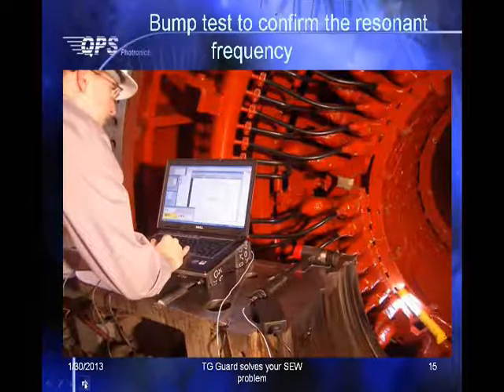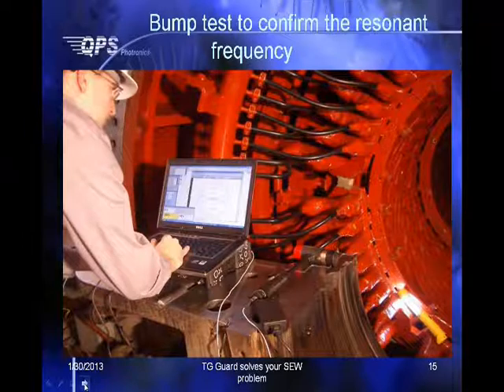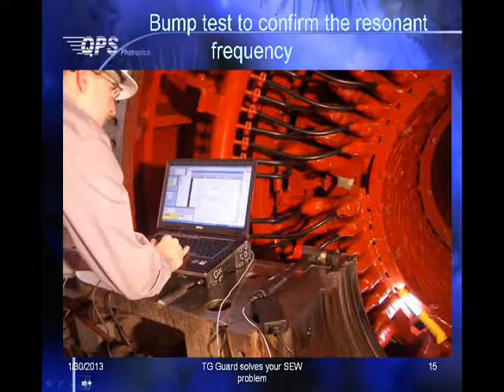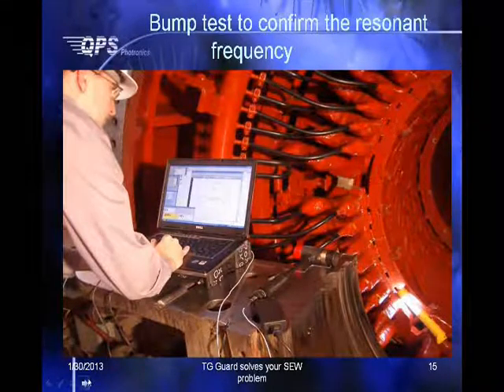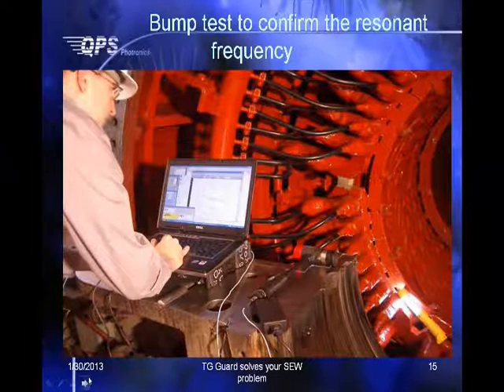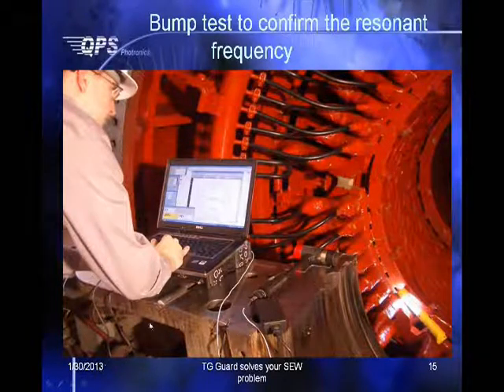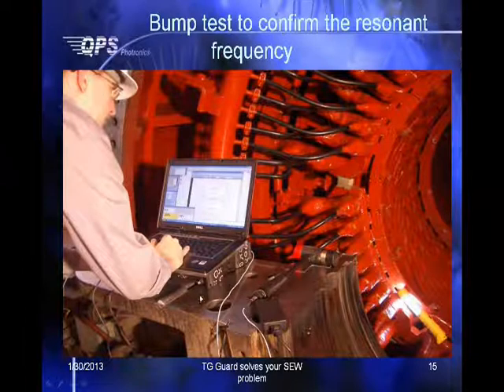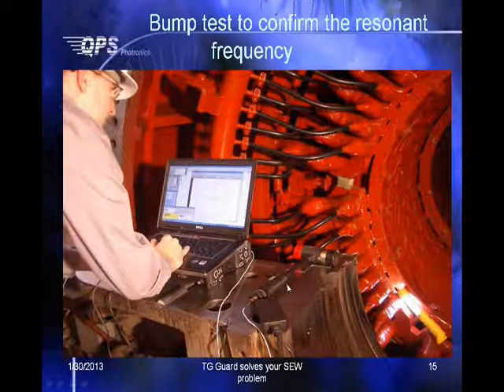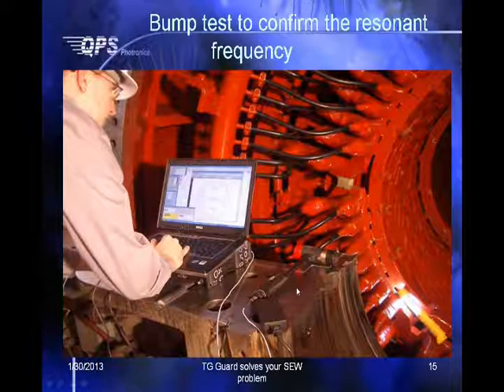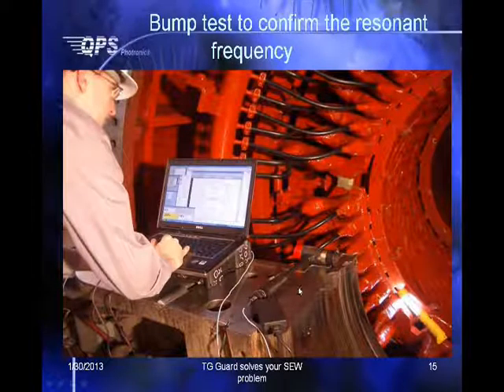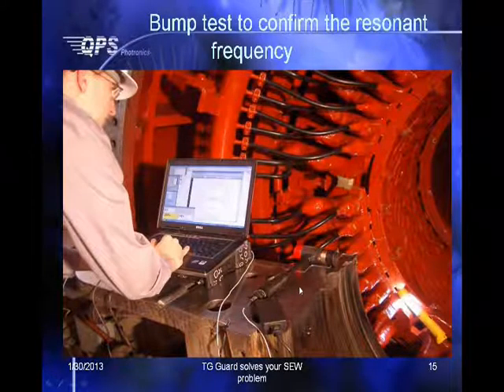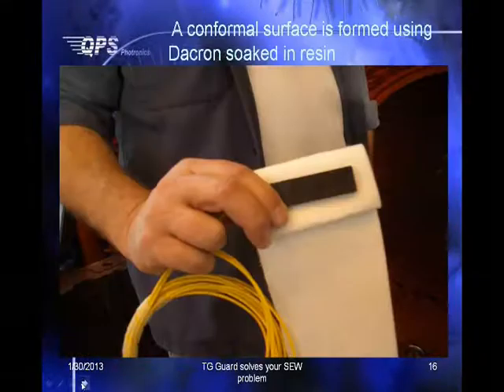The first thing we do before any installation, which is critical, is confirm that none of the end windings has a resonant frequency at 120 Hertz. Because if they do, you will have tremendous problems. At resonance, the amplitude could increase by 100 times, and that will certainly cause problems in the operation of the generator. So we did that.